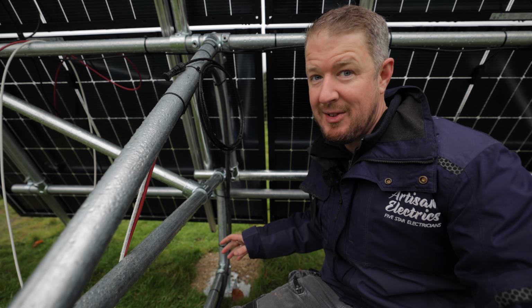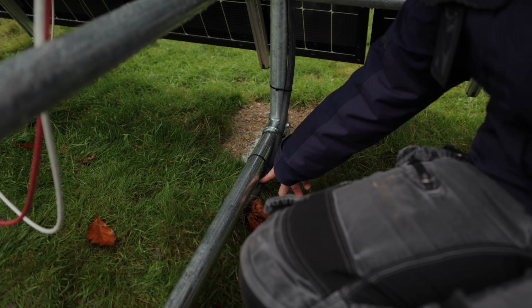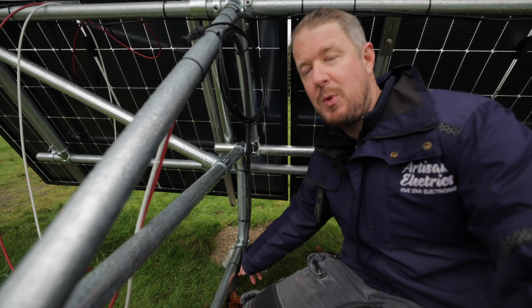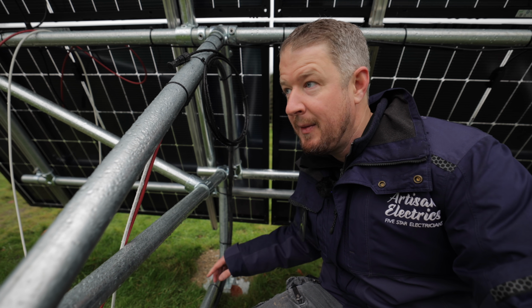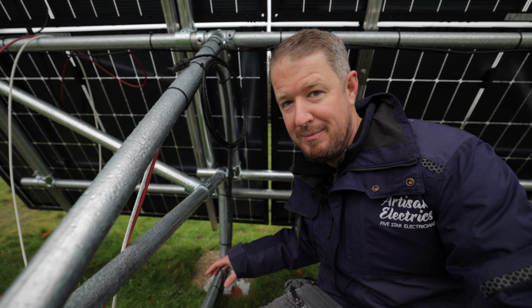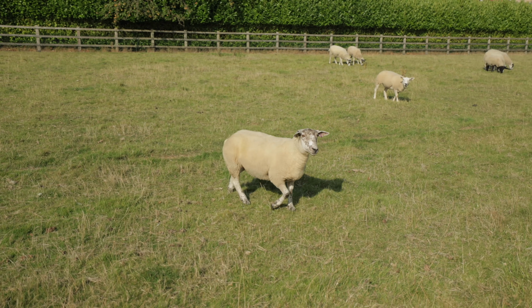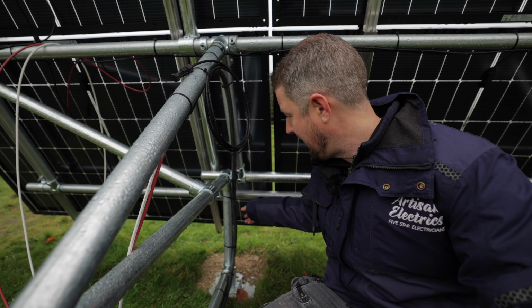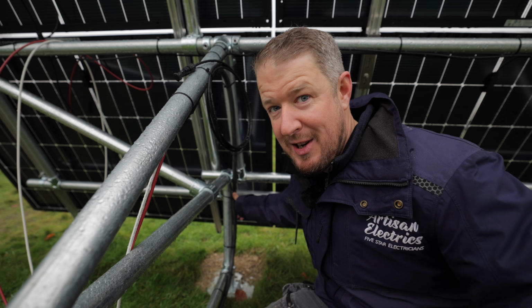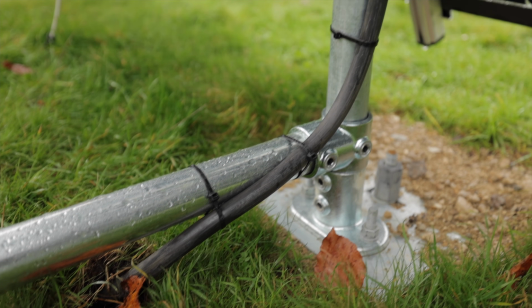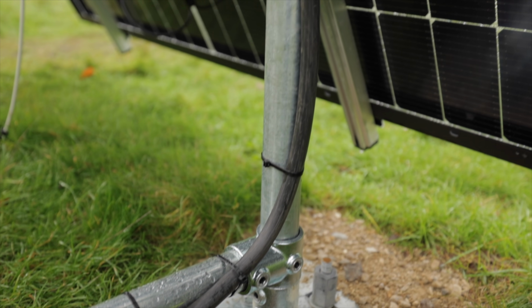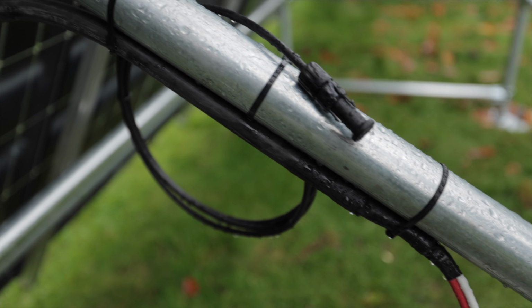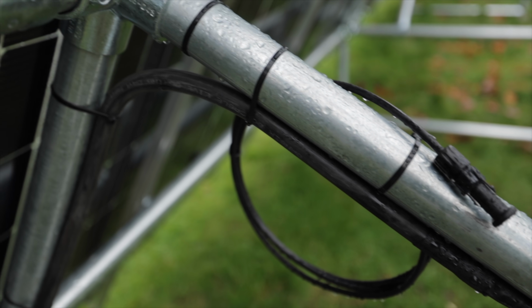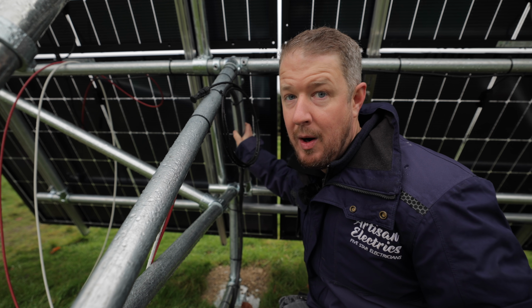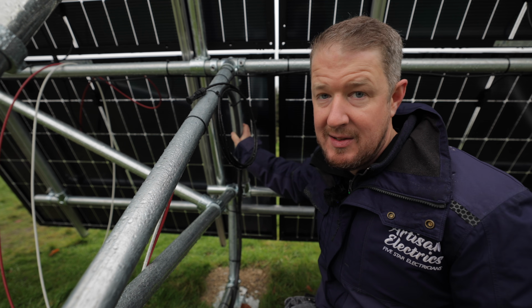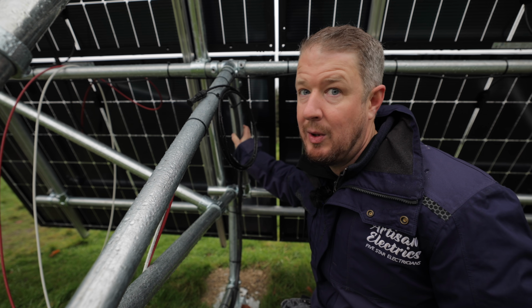The installers have very precisely brought the cables out exactly where we wanted them, just at the bottom here. But there's a problem we faced: sheep. The customer isn't going to be mowing this lawn every week - they've got sheep to do the job for them. We need to make sure these cables don't get chewed through by a hungry sheep, so we've used armoured cable with steel wire armouring inside, making it very tough. We've also kept everything else out of sheep height reach so it's protected. Another reason we use the SolarEdge system is that it's super safe - it constantly runs an insulation test, and if there's any damage to the cables, it'll instantly shut down.